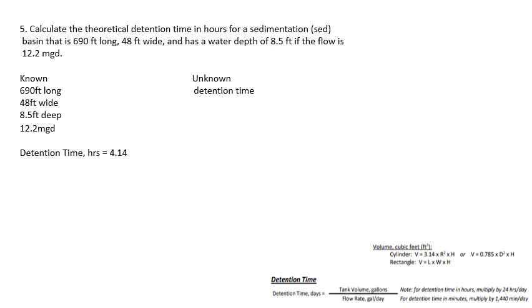Now note the theoretical detention time in this formula, pretty much solving for detention time in any flocculation basins and sedimentation basins, is theoretical because the depths can vary just on the buildup of sludge on the bottom. So it is theoretical and not exact because you don't have exact measurements.